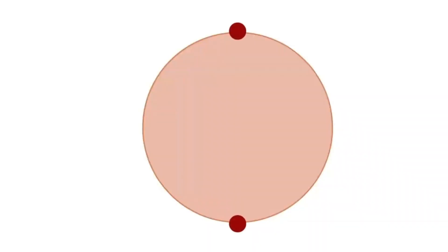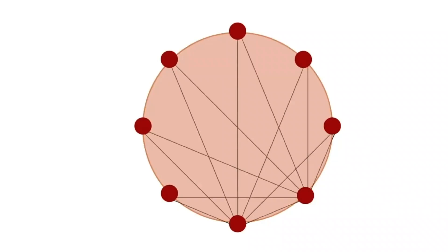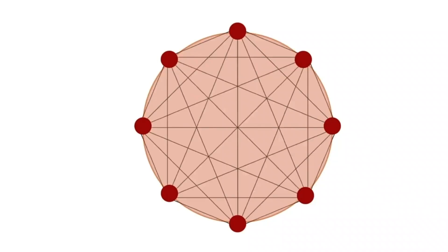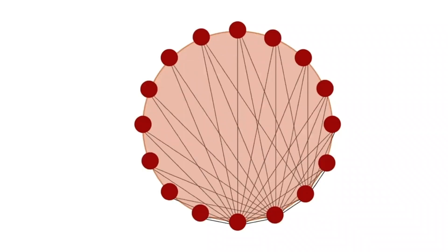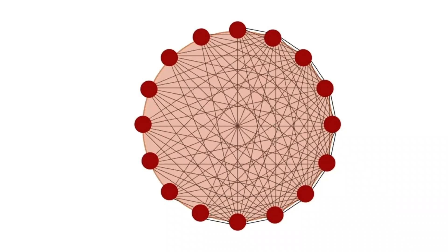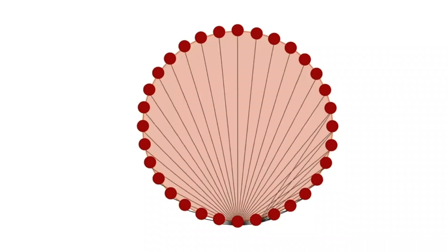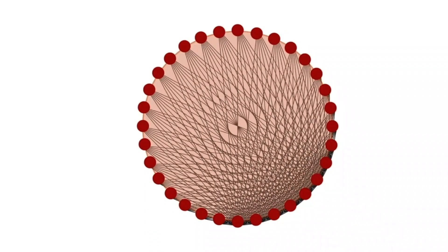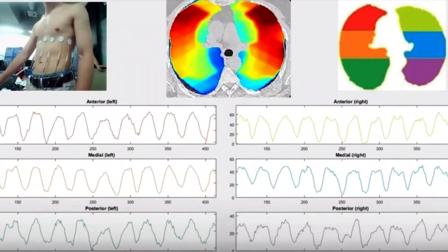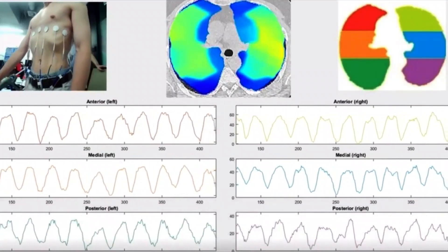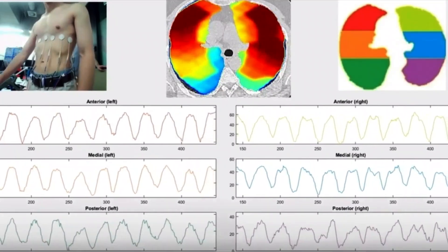This concept is based on electrical impedance tomography. What this does is create a tomographic image because of the intersection points of the different electrodes. Each red circle in this image is one electrode that emits a tiny, small amount of current, causing an equipotential change that all the other electrodes face, and at each intersection it comes together to form a tomographic image. Coupled with our machine learning algorithms, this image is then turned into a 3D illustration of the human lung.